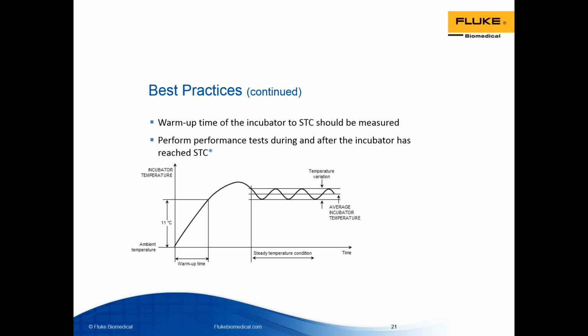You'll remember this diagram from the beginning of our webinar today, and it shows the warm-up time, the overshoot, and the oscillation to a steady temperature condition. The manufacturer's manuals will specify that warm-up time, and again, the testing should be carried out to ensure that the incubator is within the acceptable range of 20% of the warm-up time. So again, the temperature overshoot should be no more than 2 degrees above the set point. And remember that STC, the steady temperature condition, is achieved when the incubator temperature doesn't vary by more than 1 degree Celsius over a period of an hour.